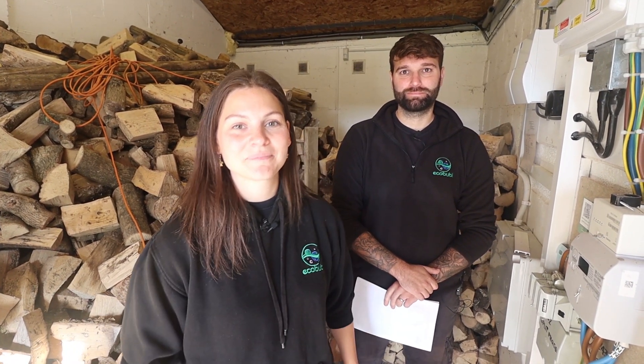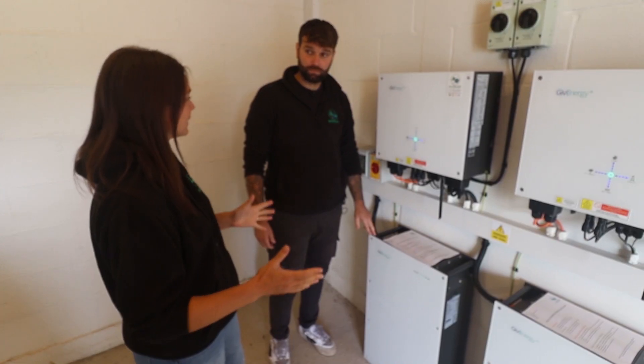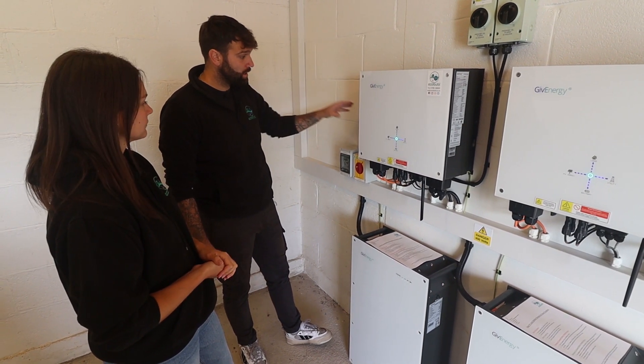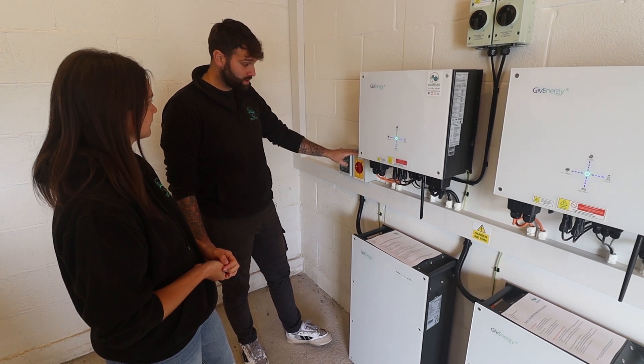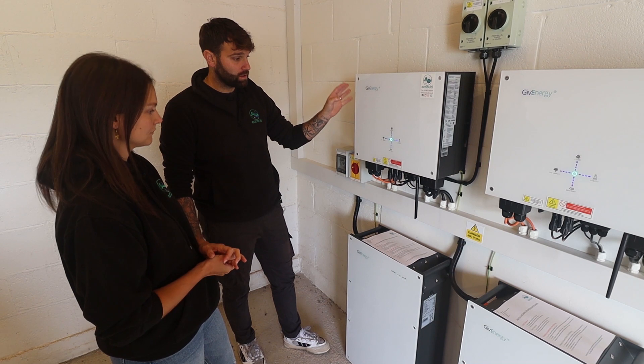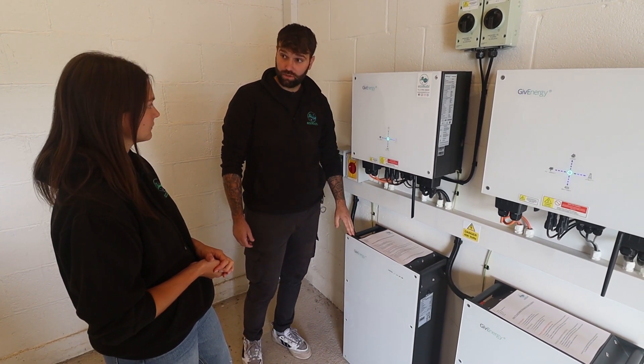Now let's go have a look at the other side where we have the GivEnergy batteries and the hybrid inverters. We come over from the AC isolator into a bi-directional generation meter and into another AC isolator, then into the GivEnergy hybrids. This is a Gen 2 hybrid inverter paired with the 9.5 kWh battery.